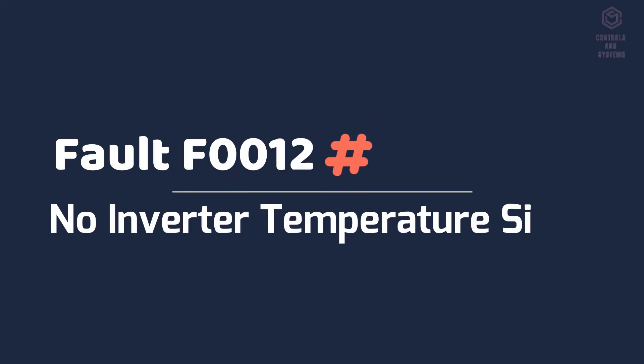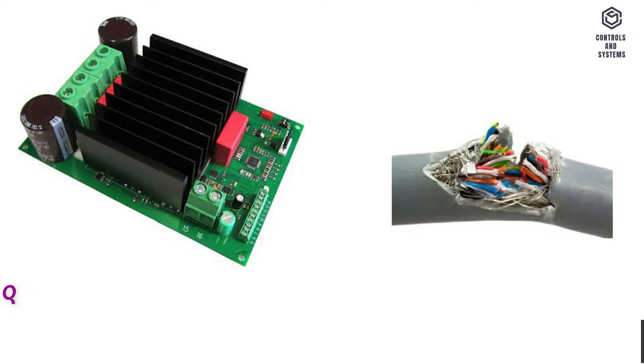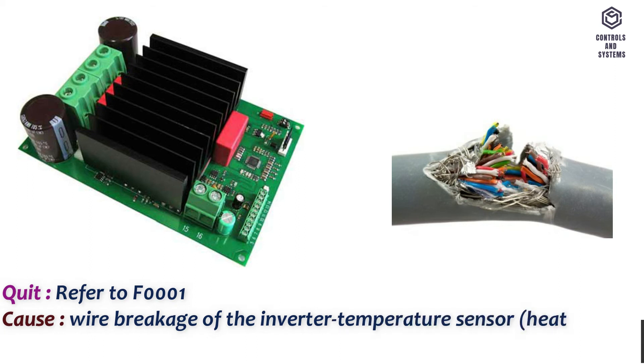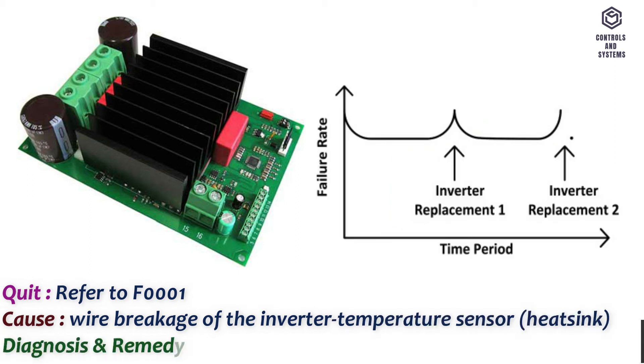Fault F0012 no inverter temperature signal. Quit: Refer to F0001. Cause: Wire breakage of the inverter temperature sensor heat sink. Diagnosis and remedy: Replace the inverter.